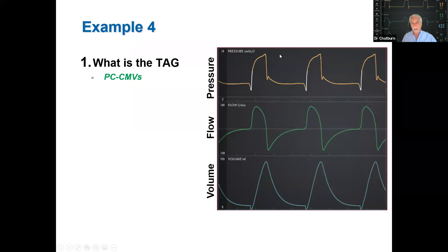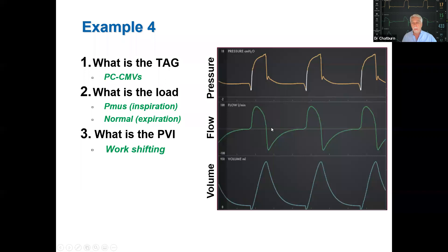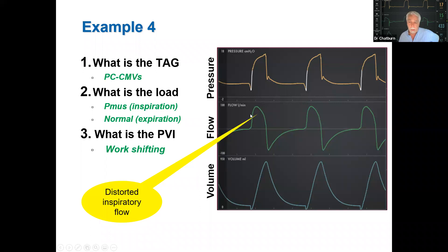Example four: pressure control, continuous mandatory ventilation — recognized from the waveform. Ventilators are not as good at controlling pressure as flow, so you will see some distortion of the flow waveform if the patient makes inspiratory efforts. The load shows muscle pressure during inspiration — increased over what we'd expect for an exponential decay — while expiration shows a normal exponential decay. We call this work shifting because of the distorted inspiratory flow and augmented tidal volume. In such a situation, you might get an excessive tidal volume above a safe limit of 6–8 mL/kg.